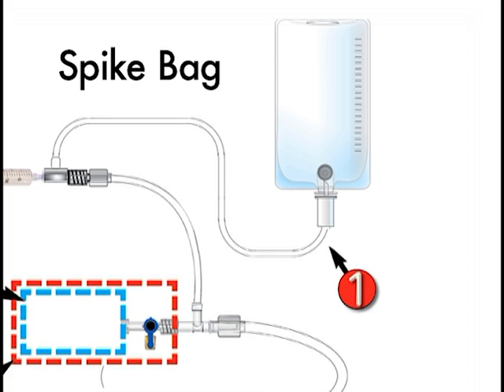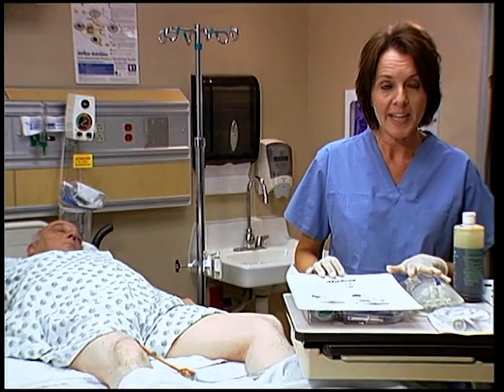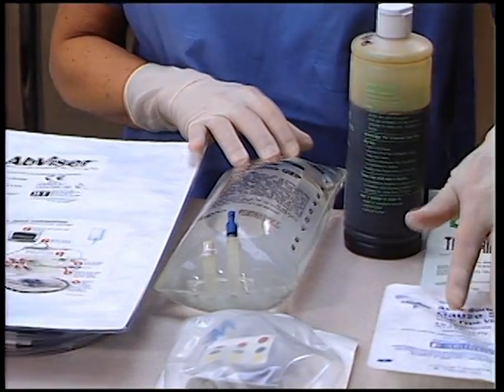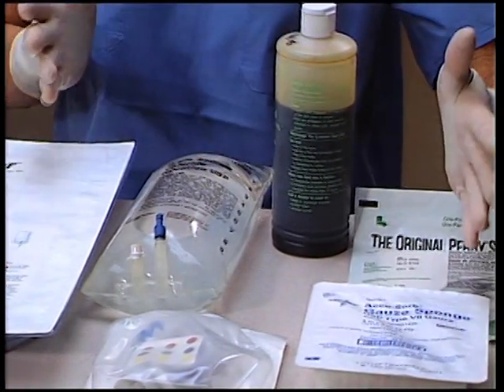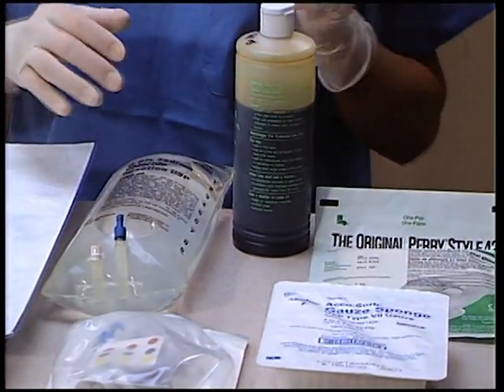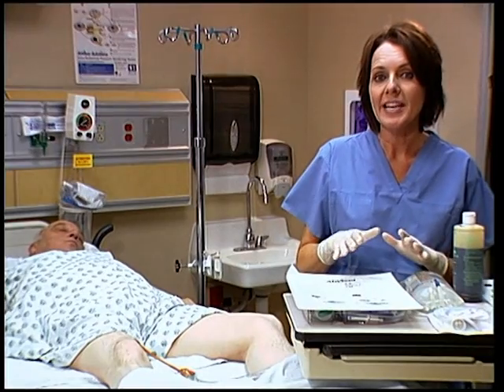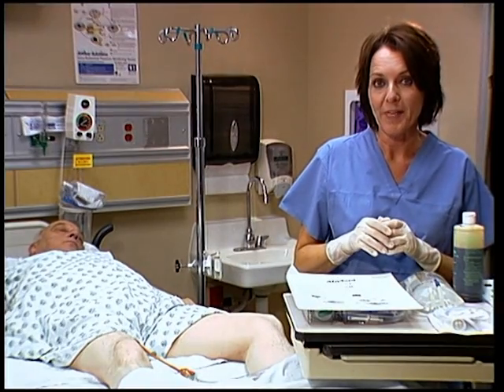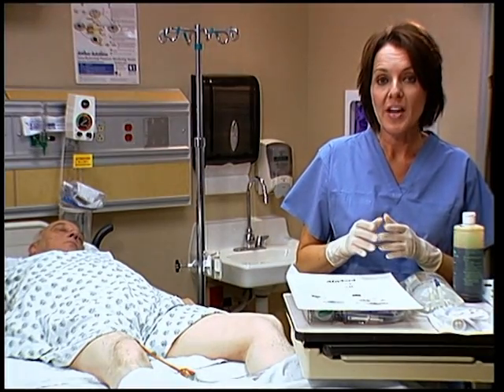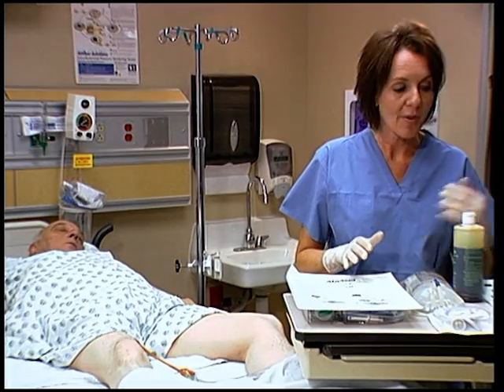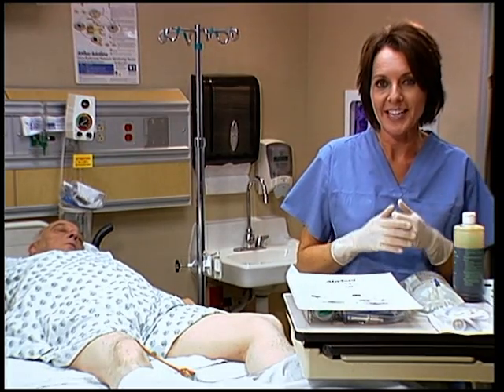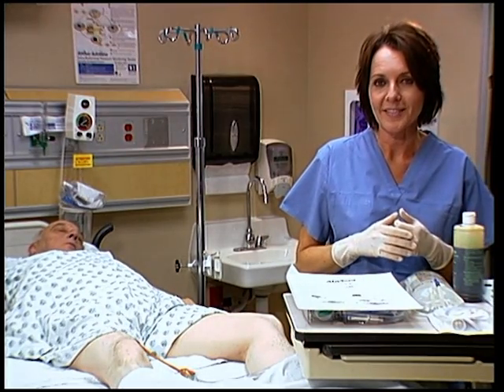To set up the AbVisor, you will need a 1-liter saline bag and an antiseptic solution, a 4x4 tray with sterile gloves, and a standard arterial line transducer. If you intend to patient-mount the transducer, you will also need a 4x4 pad and some tape for attaching the transducer to the skin of the patient.